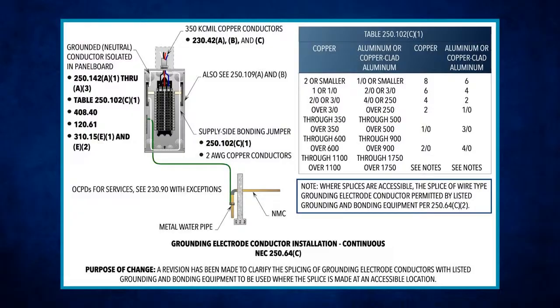Yeah, and when you look at that and you go over and you look at 250.66(C), what gets me is that it talks about the grounding electrode conductor or bonding jumper that's connected to a ground ring. And this is why I have an argument with this, because it says as described in 250.52(A)(4). And when you go pick up 250.52(A)(4), it says it has to be what? Number 2. Yeah, number 2. And that's why I'm like, it tells you here, if the grounding electrode conductor or bonding jumper is connected to a ground ring as described in 250.52(A)(4), that's a number 2.